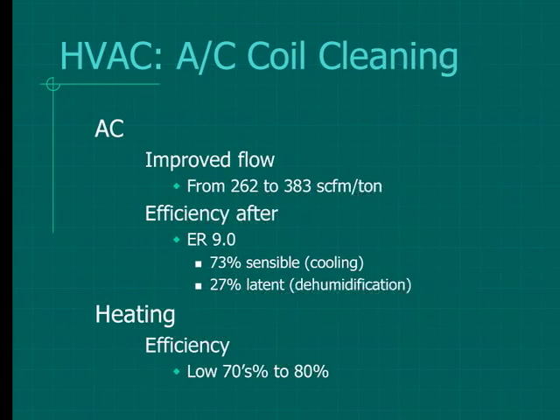For the engineers in the room, we can go over the numbers. Cleaning the coil, we actually changed out a filter also. The flow went from 262 to 383 standard cubic feet per minute per ton. Now you're saying, what's that? Let me just tell you, nominal is 400. In Colorado, we like to see 450, 480. So we still didn't quite get to where we wanted to be, but we're a whole lot closer.